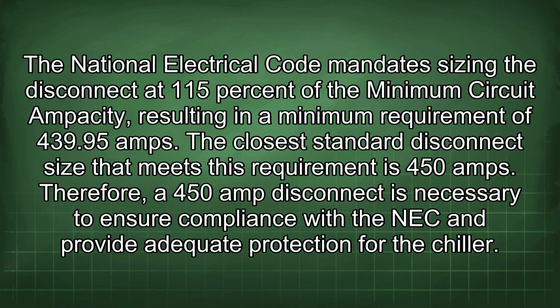The National Electrical Code mandates sizing the disconnect at 115% of the minimum circuit ampacity, resulting in a minimum requirement of 439.95 amps. The closest standard disconnect size that meets this requirement is 450 amps. Therefore, a 450 amp disconnect is necessary to ensure compliance with the NEC and provide adequate protection for the chiller.